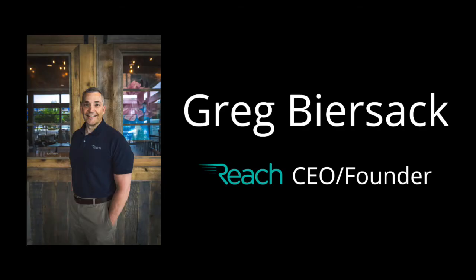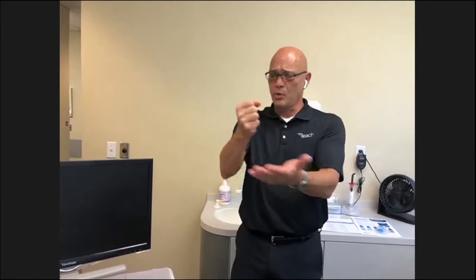Darold, we've got another question. What are your thoughts around handheld x-rays? Handheld x-rays are coming more and more in offices that we're seeing. There is more flexibility, as you can take one handheld x-ray to multiple operatories, of course, versus having to have an x-ray in every hygiene room. It is a learning curve to be able to hold that correctly. So you definitely want to go through some training with your equipment specialist from whatever supply house you use. But it's a learning curve.